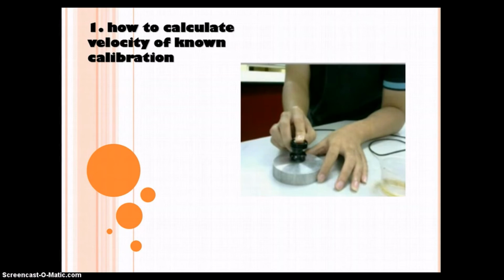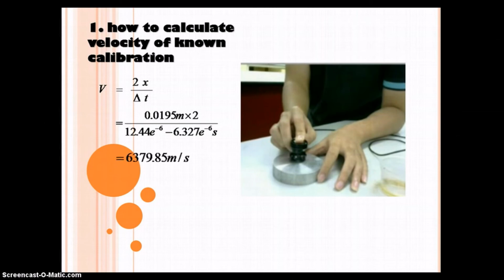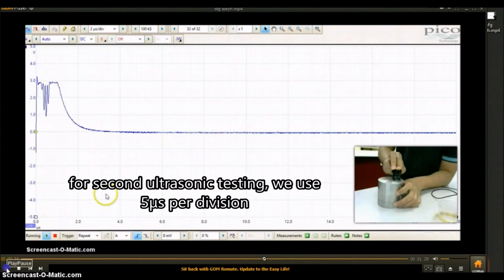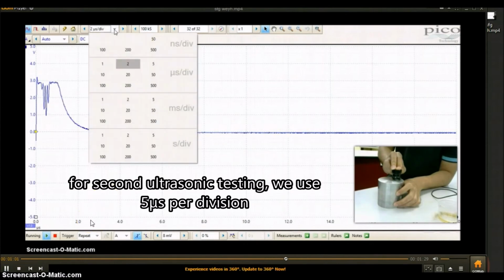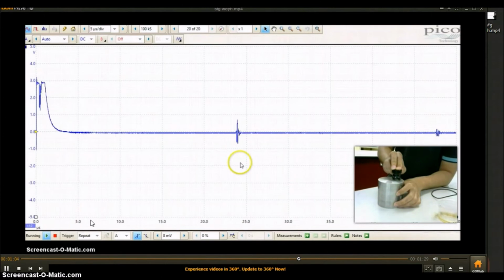The first step of ultrasonic thickness measurement is to calculate the velocity of the known calibration using the formula V equals 2x over delta T. Using the known thickness, we get 0.0195 meter multiplied by 2 and divided by 12.44 times 10 to the power of negative 6 minus 6.327 times 10 to the power of negative 6 seconds. The answer is 6379.85 meters per second.